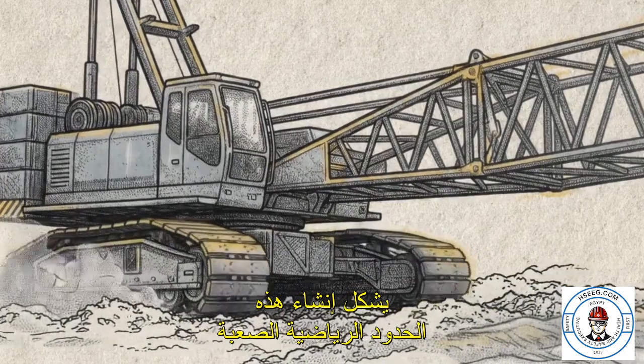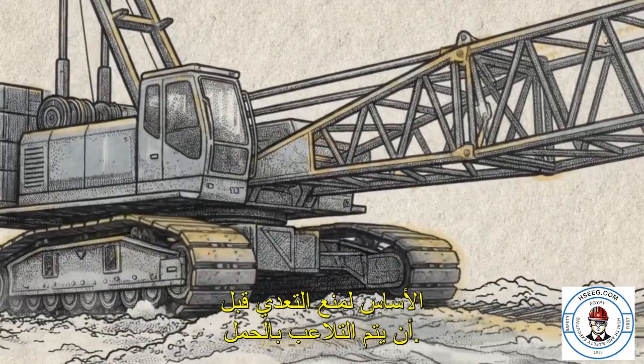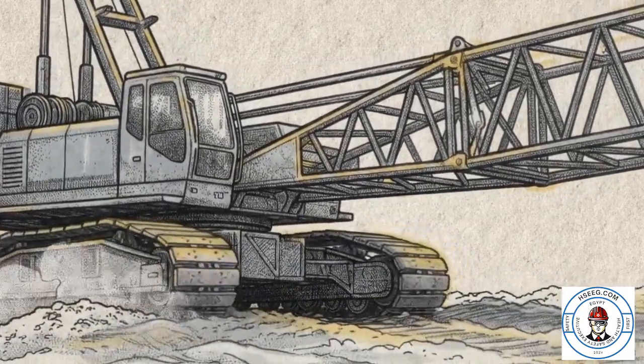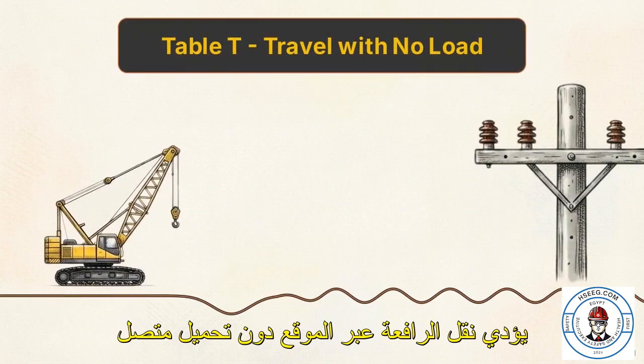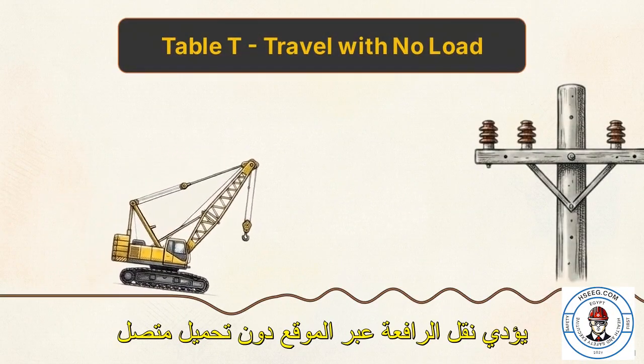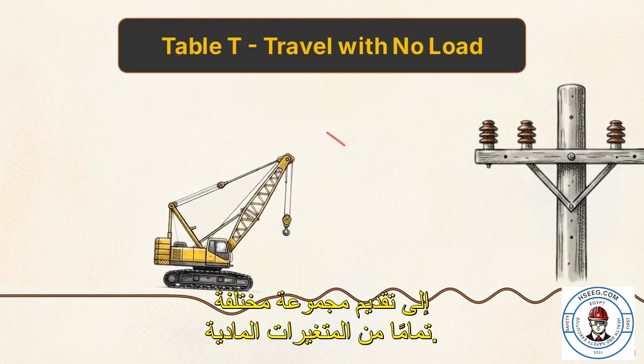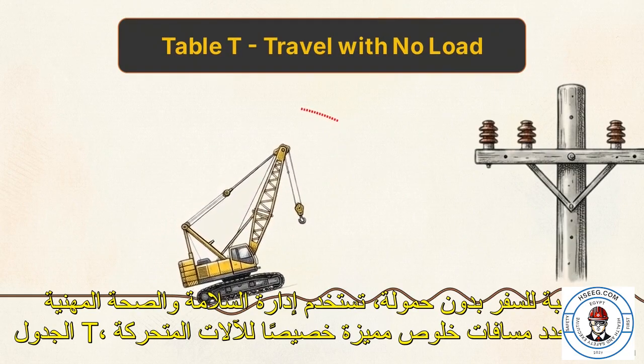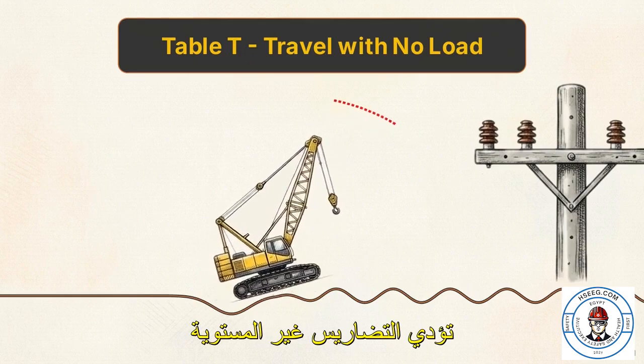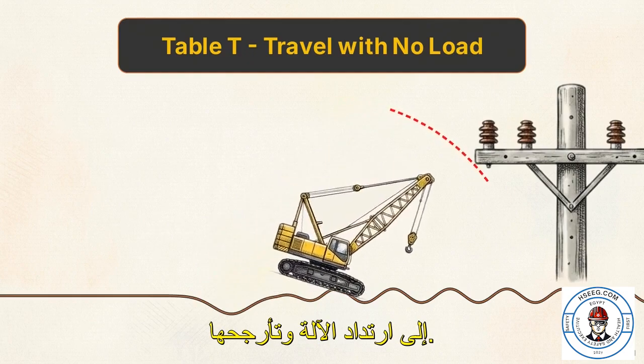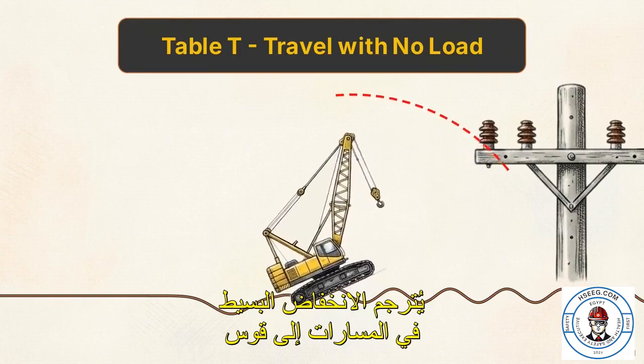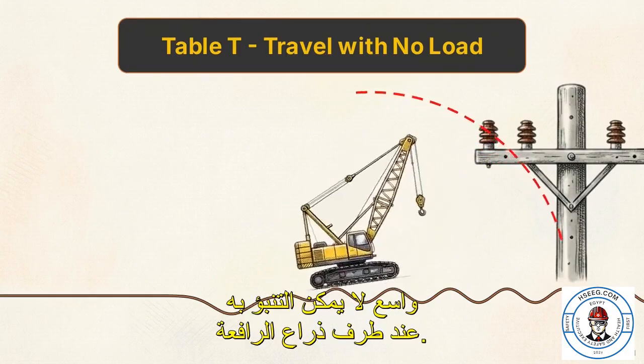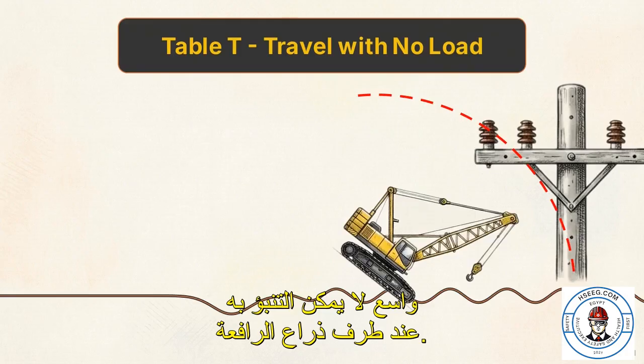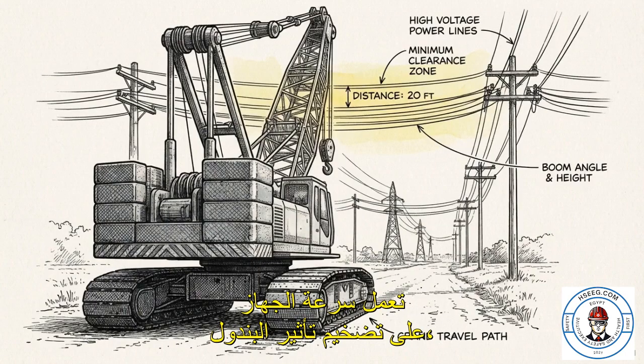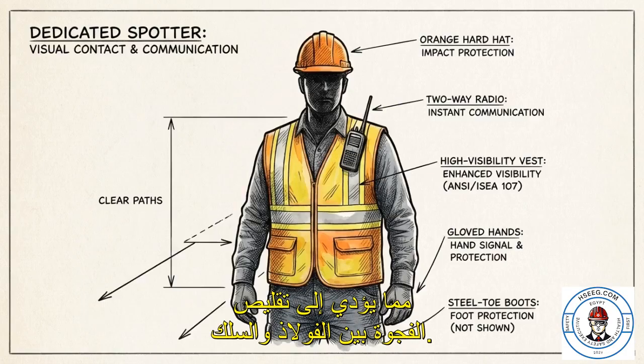Moving a crane across a site without a load attached introduces an entirely different set of physical variables. For unladen travel, OSHA utilizes Table T, which dictates distinct clearance distances specifically for machines in motion. Uneven terrain causes the machine to bounce and sway. A small dip at the tracks translates into a wide, unpredictable arc at the tip of the boom. The speed of the equipment magnifies this pendulum effect, shrinking the gap between the steel and the wire. If the crane's travel path could bring any part of the machine within 20 feet of the line, the use of a dedicated spotter becomes legally required.